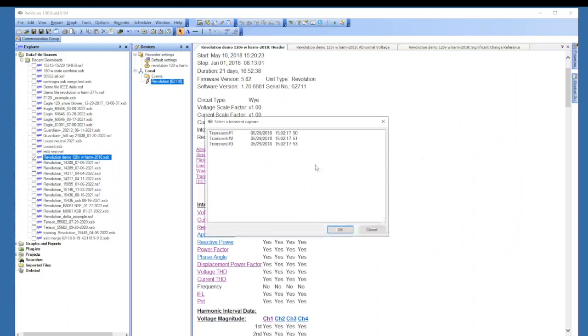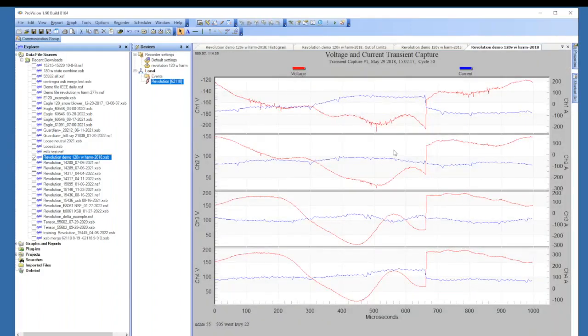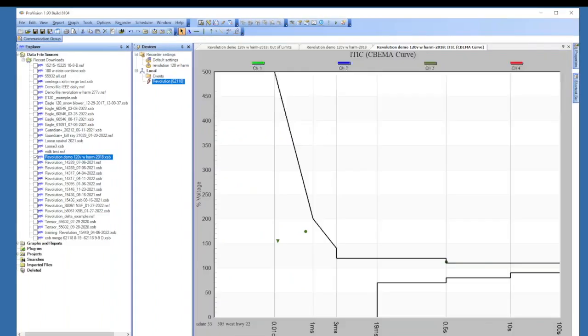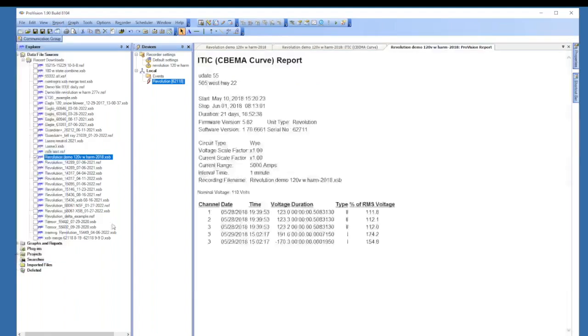Transient captures. Again, the revolution will do transient. So you can see it's in microseconds at the bottom. So basically pretty close to 1/3 of a cycle is what you'll see there. And the ITIC don't have a whole lot going on there. But if you go under the report tab and choose the report for that, you can see when those occurred.